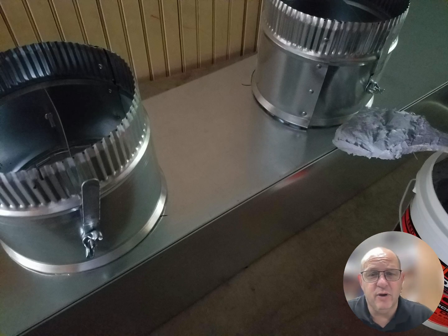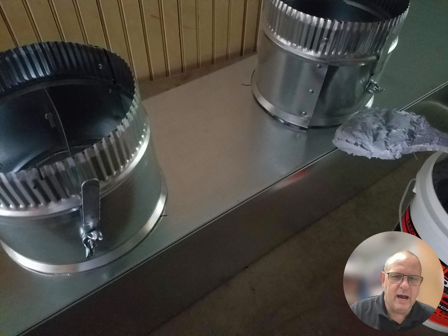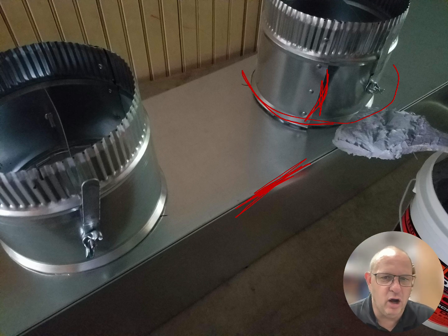Okay, now it's time for us to put the mastic on this fitting. As I'm going to show you in the next picture, I've painted the entire thing, but any gap that you see within this ductwork is a place for air to come out. So I will paint the entire perimeter of this ductwork. I will paint up this seam right here. I will paint the seam that's on the square ductwork or the main trunk as it's coming off. But I want to be careful that I don't put that mastic on that damper. That's going to inhibit that damper from moving from a parallel to a perpendicular form so that we can get that airflow through there freely.